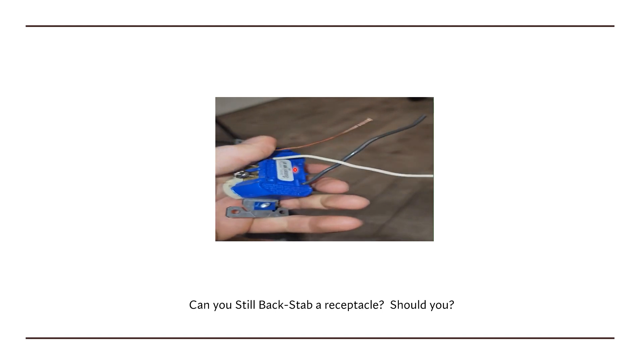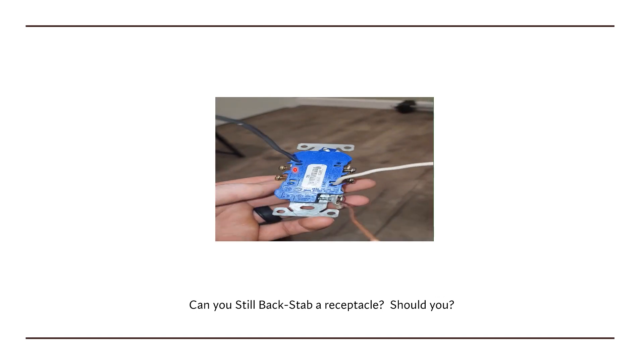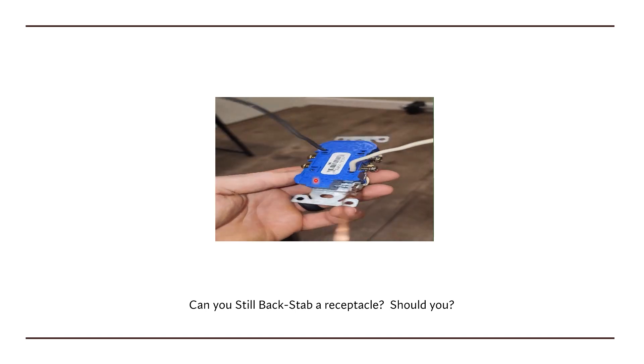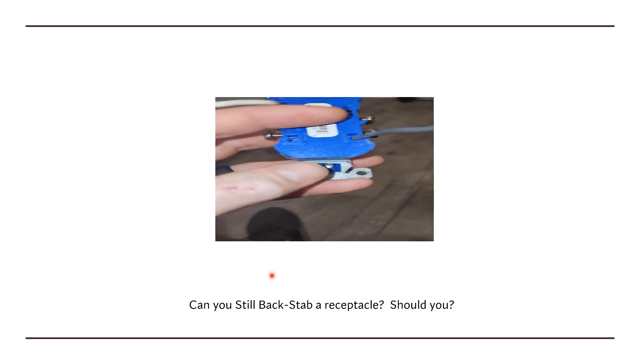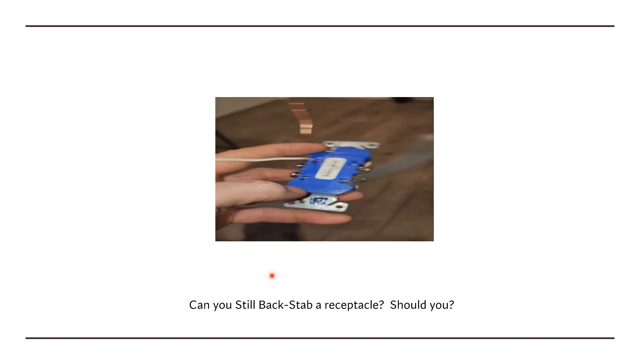Now let's talk about some of the reasons we maybe shouldn't use backstab. So I'm not going to knock you if you do use it. We're going to talk about some of the comparisons here in just a moment. But I want to let you know that almost every time that I come to someone's home and I'm troubleshooting receptacles, it's because they were backstabbed. It's a much stronger and preferred connection to wrap around the screw properly, torque it down and tighten it. But backstabs cause a lot of trouble.